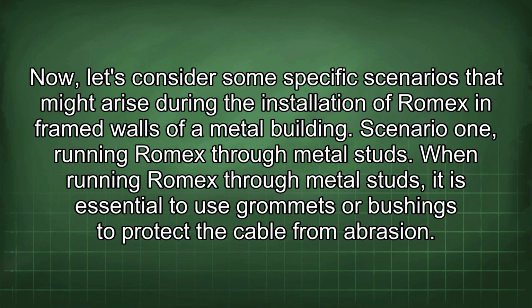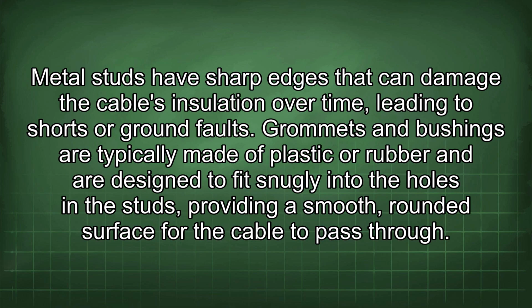When running Romex through metal studs, it is essential to use grommets or bushings to protect the cable from abrasion. Metal studs have sharp edges that can damage the cable's insulation over time, leading to shorts or ground faults. Grommets and bushings are typically made of plastic or rubber and are designed to fit snugly into the holes in the studs, providing a smooth, rounded surface for the cable to pass through.